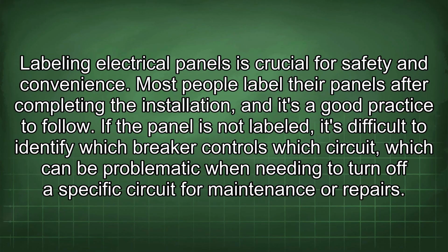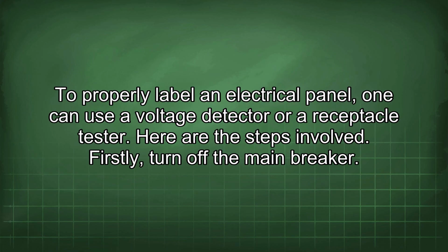Labeling electrical panels is crucial for safety and convenience. Most people label their panels after completing the installation, and it's a good practice to follow. If the panel is not labeled, it's difficult to identify which breaker controls which circuit, which can be problematic when needing to turn off a specific circuit for maintenance or repairs. To properly label an electrical panel, one can use a voltage detector or a receptacle tester.